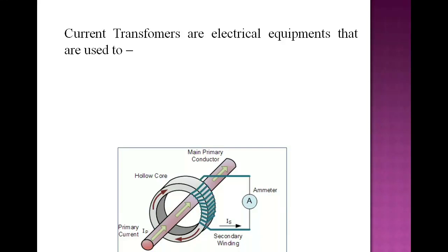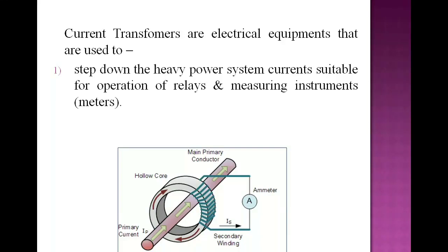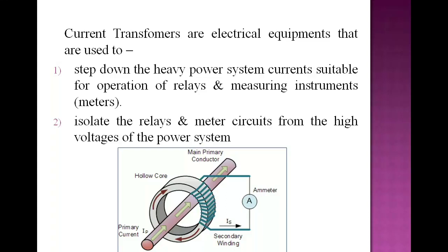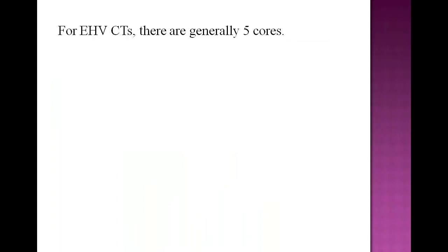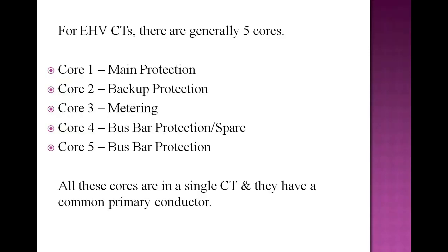Current transformers are electrical equipment used for two reasons: to step down heavy power system current to values suitable for operation of relays and measuring instruments, and to isolate the relays and meter circuits from the high voltages of the power system. For EHV CTs, there are generally five cores — first for main protection, second for backup protection, third for metering, and fourth and fifth for bus bar protection. All these cores are in a single CT with a common primary conductor.